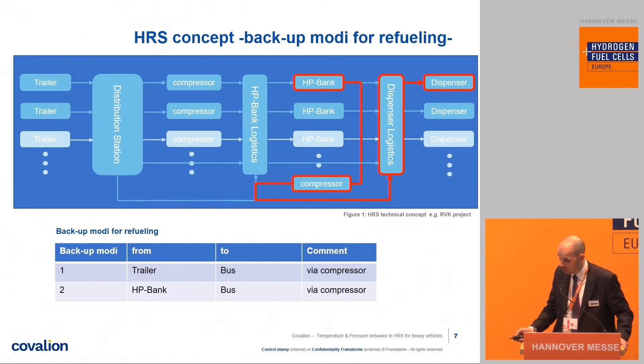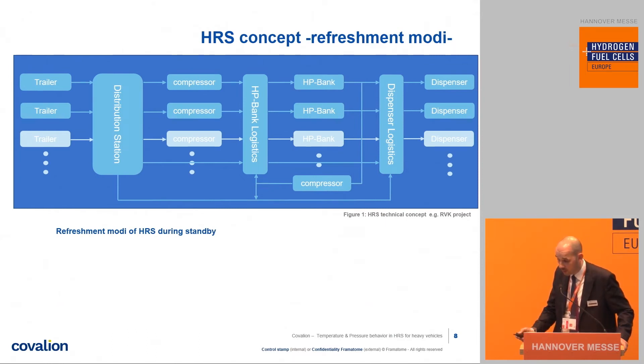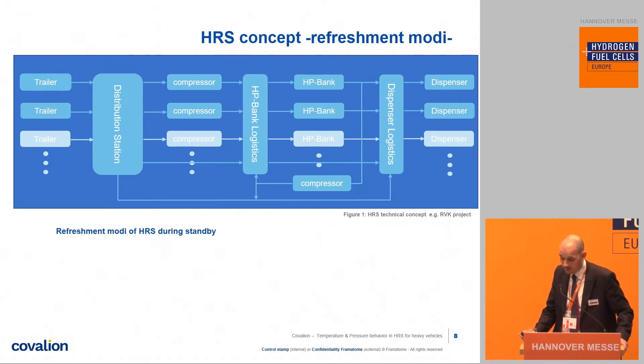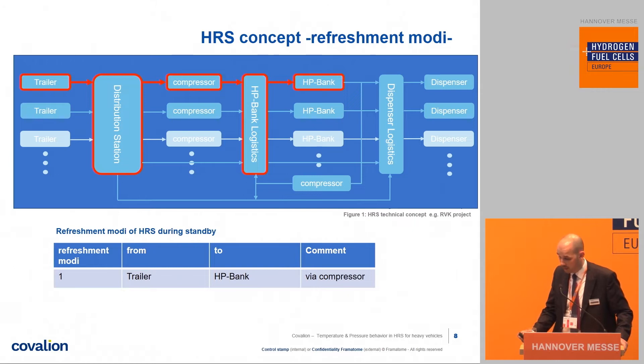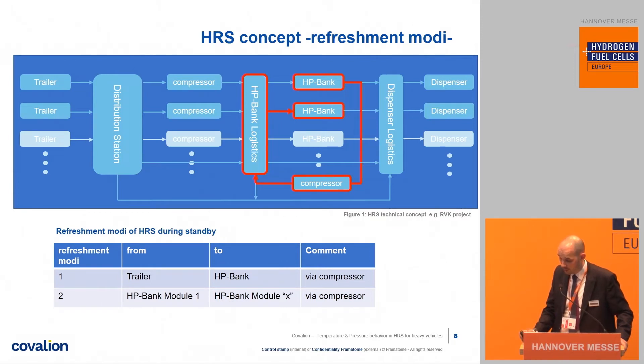Similarly, if the pressure level is too low in the hydrogen bank, we can use the compressor unit to refill the bus. There is a third mode I call the refreshment mode. It operates during standby — when no bus refueling is ongoing. If there is a low level in one of our pressure vessels, for example in the trailer, we can use the compressor unit to bring hydrogen to a higher pressure in the HP bank, or we can do a shuffle mode, moving hydrogen from a low-pressure bank through the compressor to a higher pressure level.